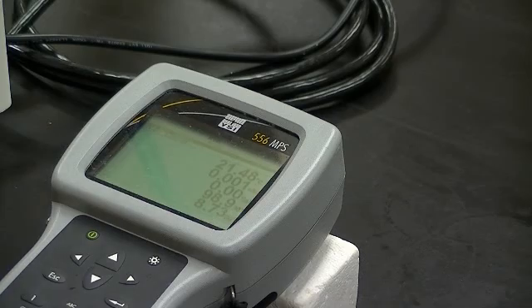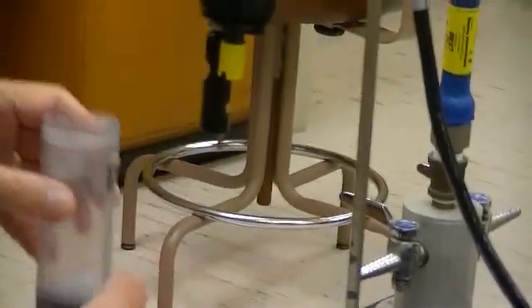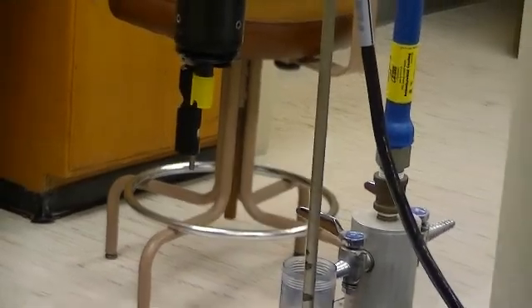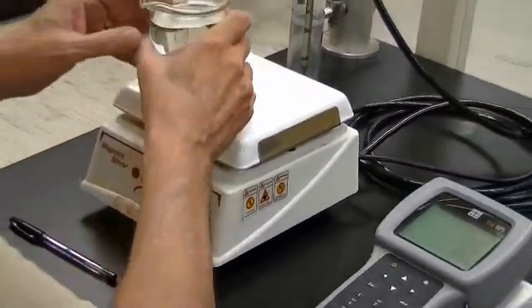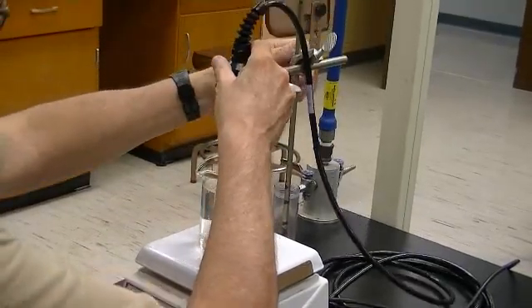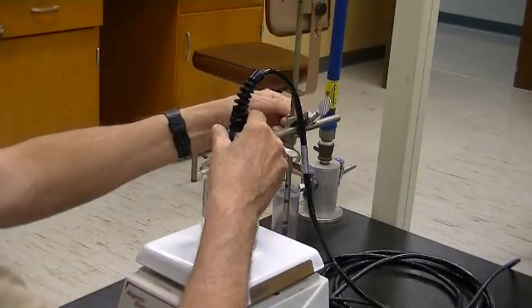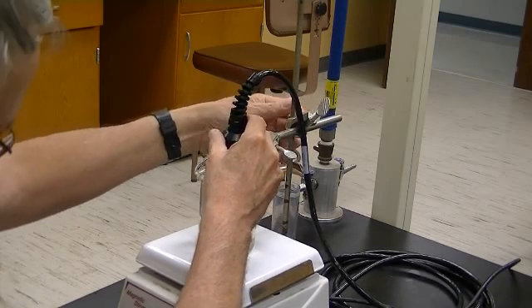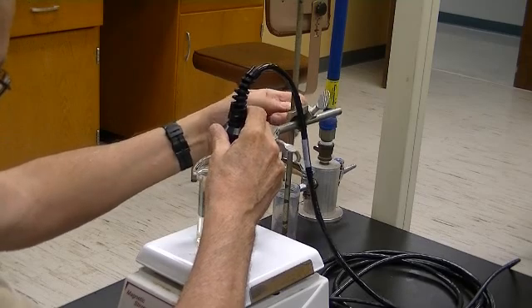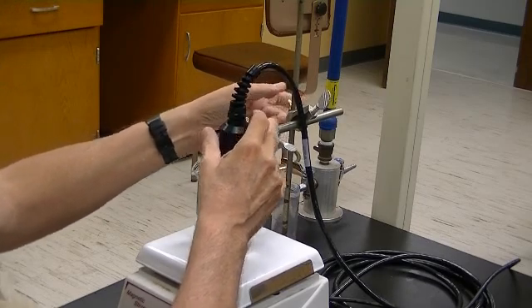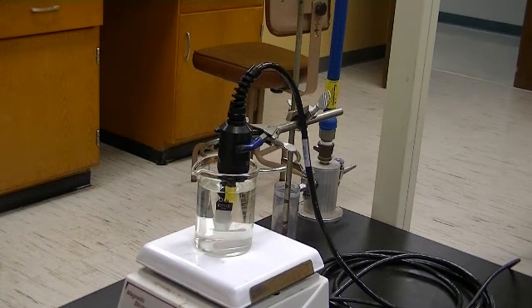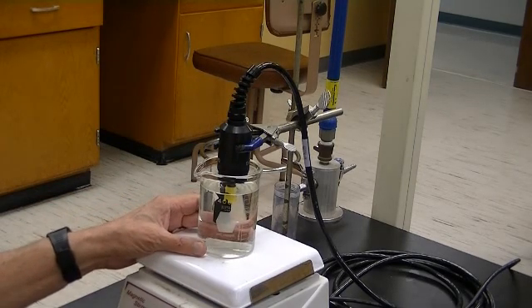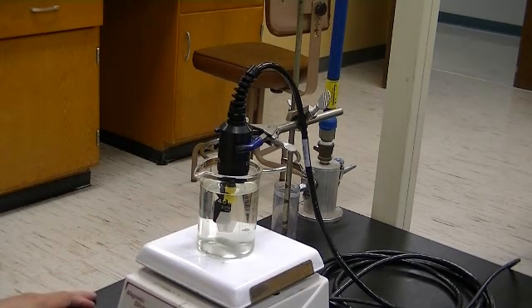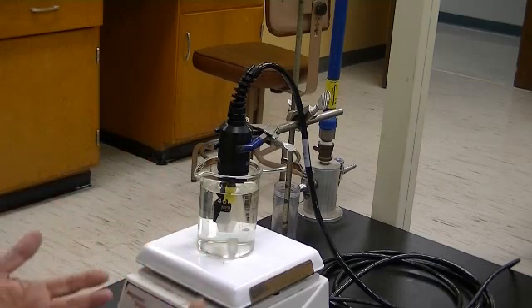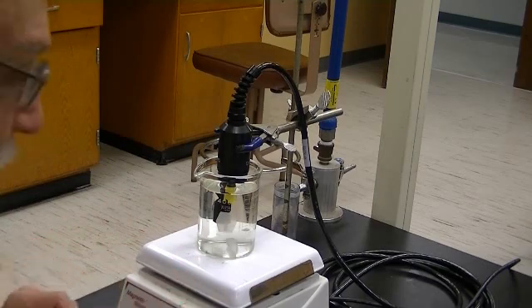Okay. Now at this point, take this off. Now it's calibrated. Now here's some water from the jug with a spin bar in it. And you just lower the probes until the yellow probe is submerged. But the end of the yellow probe is all it has to be submerged. That's where the membrane is. And you want to keep the salinity probe from hitting the spin bar. And now you turn it on just very gently like that. You don't want to pull a vortex when you spin it, because now we're measuring oxygen, and if you really disturb it a lot, it will change the oxygen.